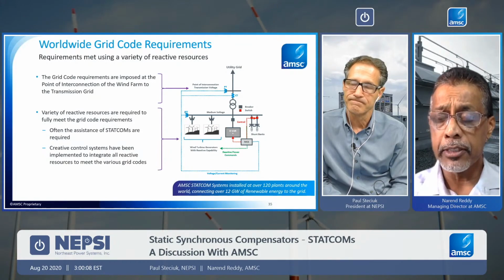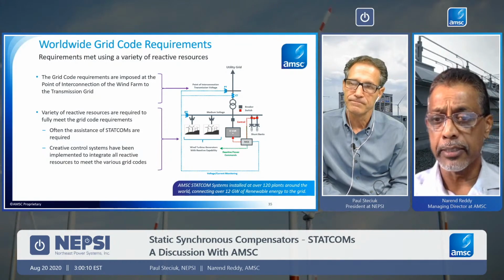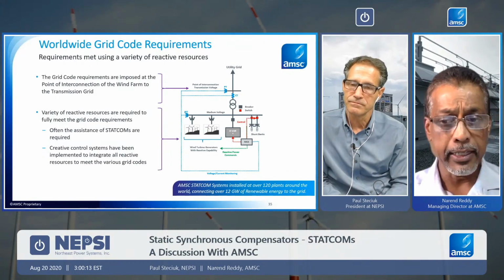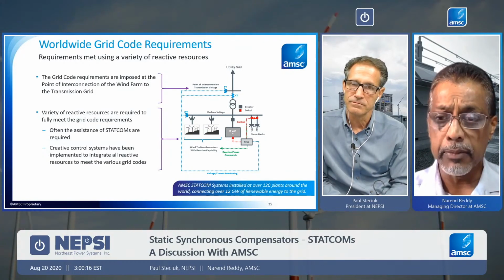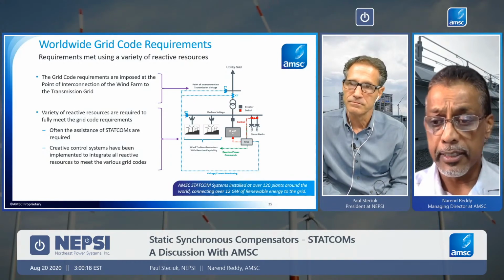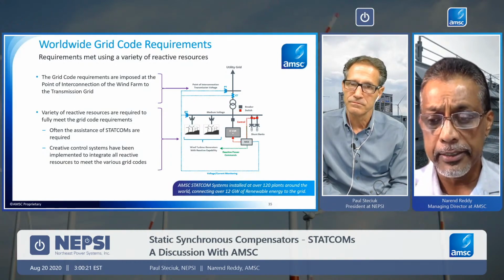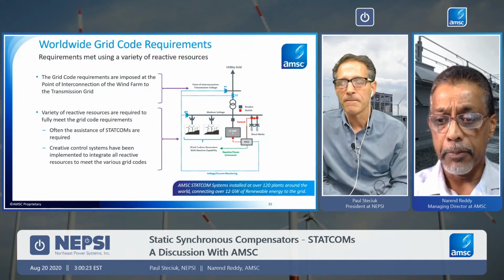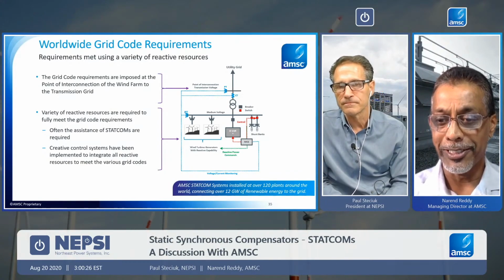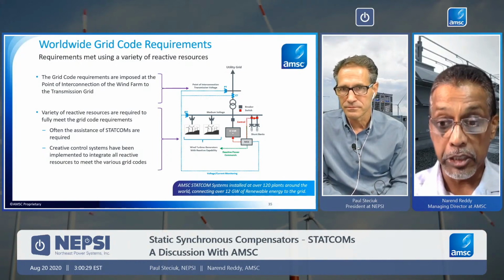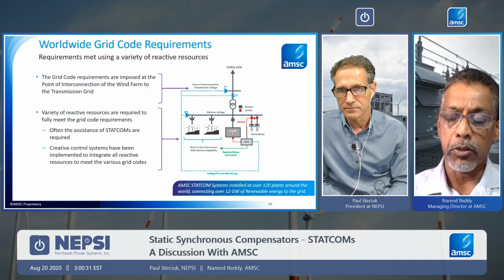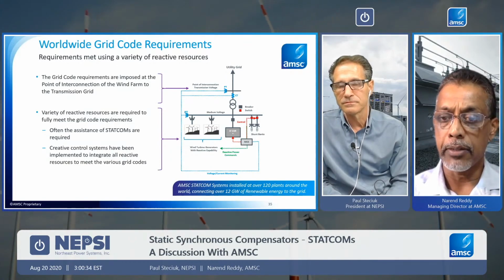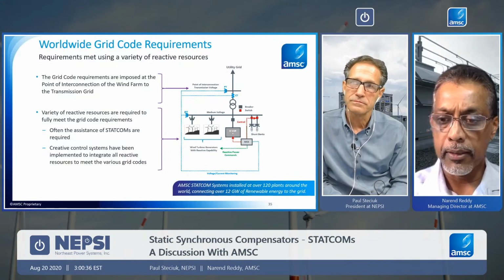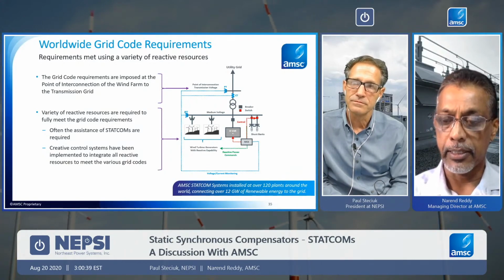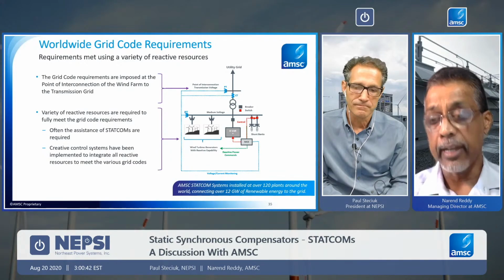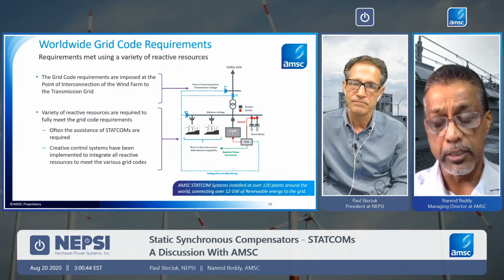Now, if the turbine capability is sufficient, or the turbines have all of the dynamic capability and the speed of response capability that they need. Don't forget, these are turbines that are spread over, as I mentioned, many miles apart. But if you want to get all of the response at the same time, that can be challenging in a lot of respects. So all that needs to be modeled and understood about where the gaps might be in terms of the final connection point performance.